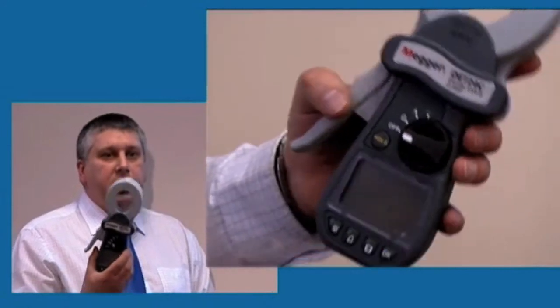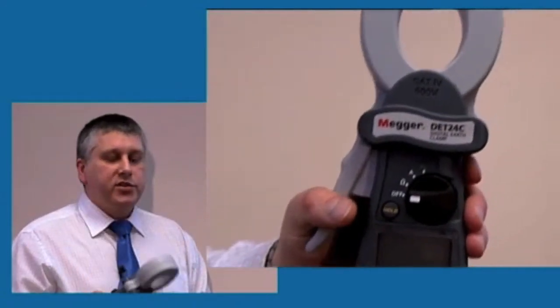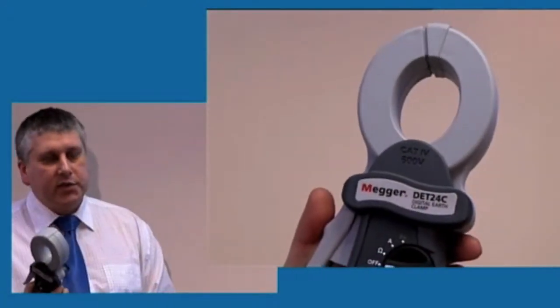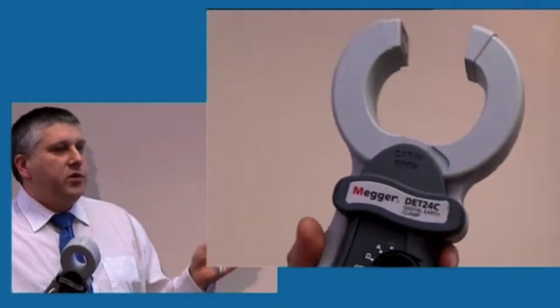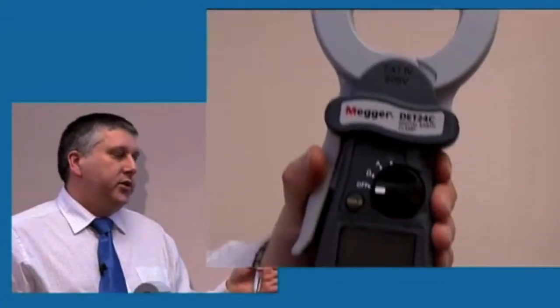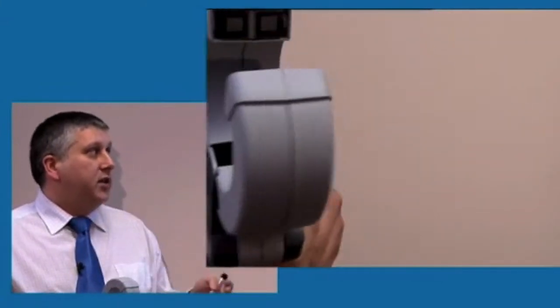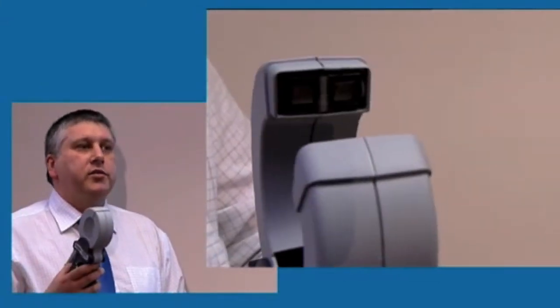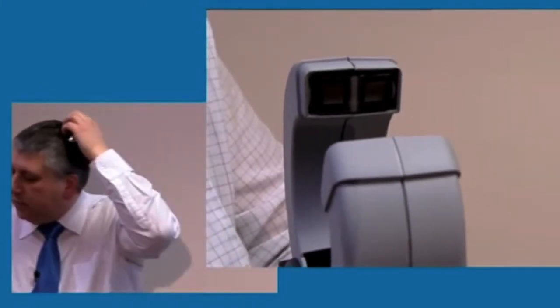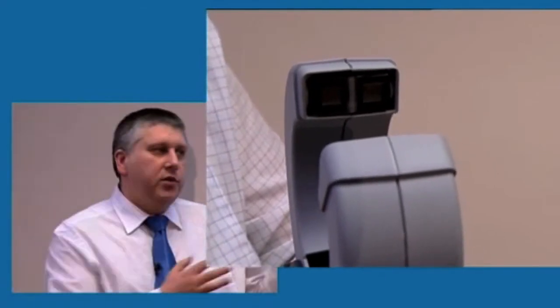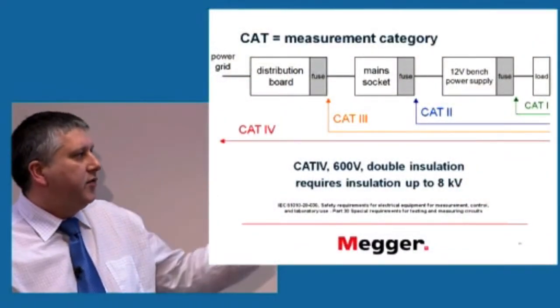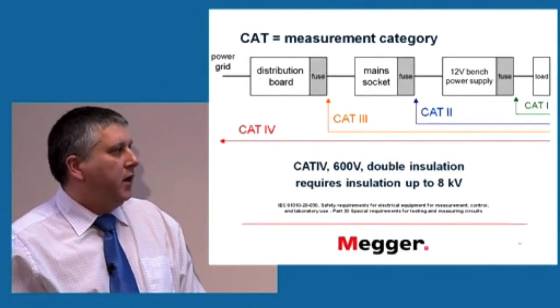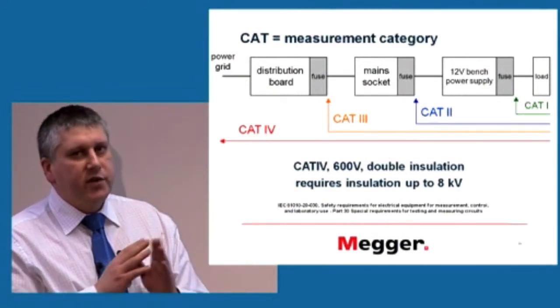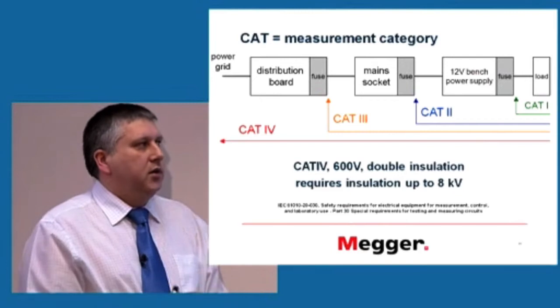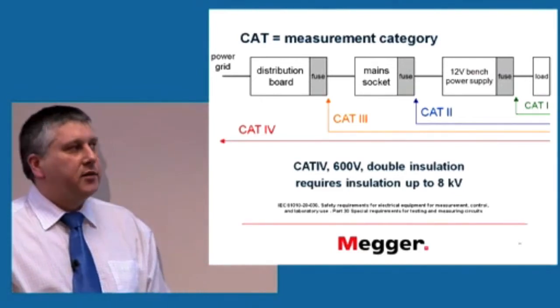600 volts, it means that it has to have double insulation everywhere between any parts the user can touch, which means for voltage spikes and other things that the required insulation is 8 kilovolts between the parts the user can touch and the rest of the circuit. And this is defined by the international standard IEC 61010, which is a very, very specific definition of how this has to be met.